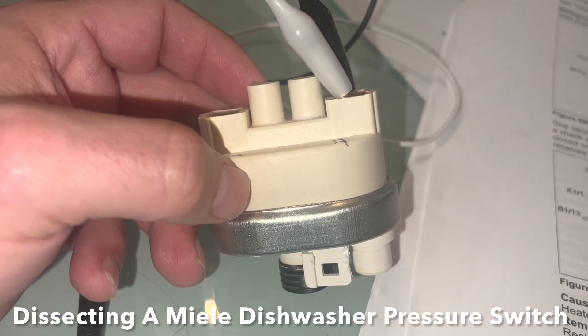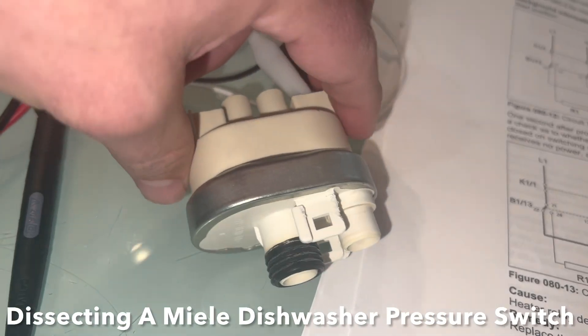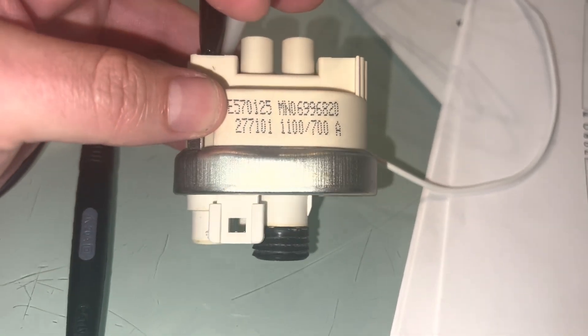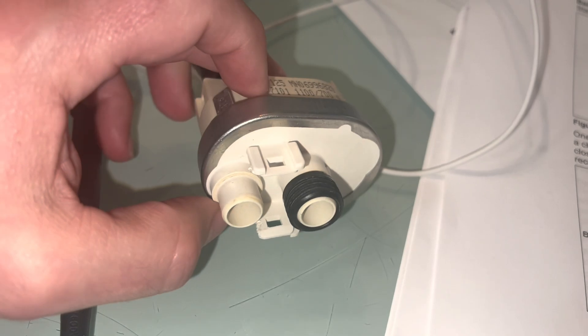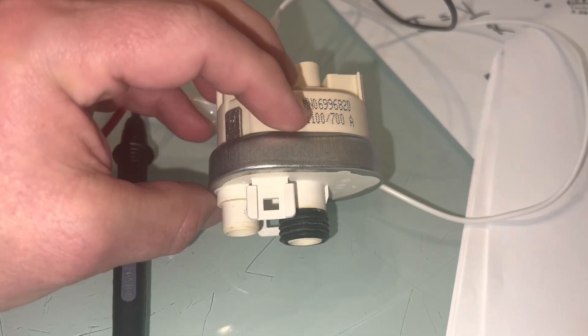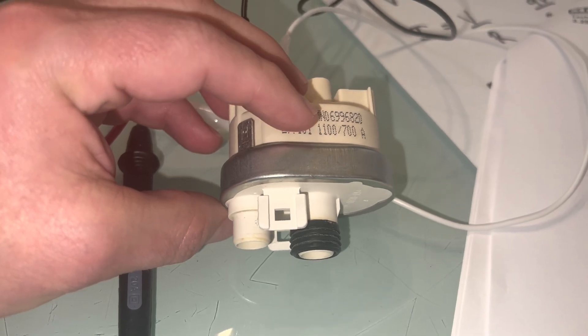I'm continuing to try to understand what went wrong with my pressure switch. What I did is put it in the freezer for about 20 minutes, and I found out that I couldn't depress the diaphragm anymore. So I'm suspecting that there's water or something that froze behind it.